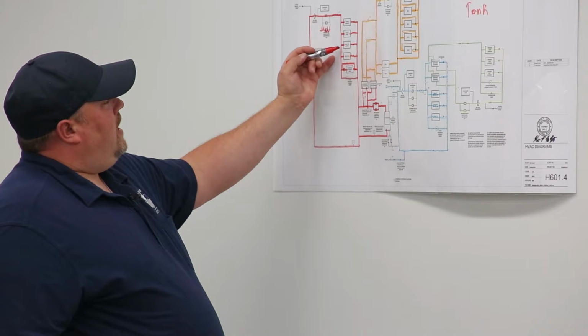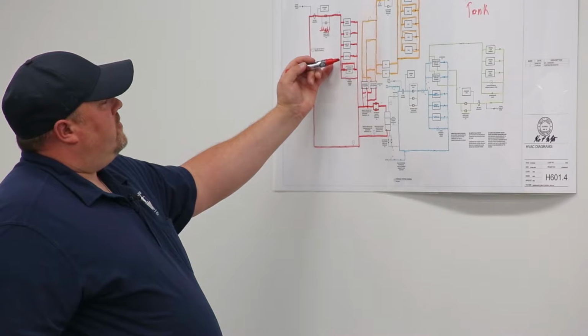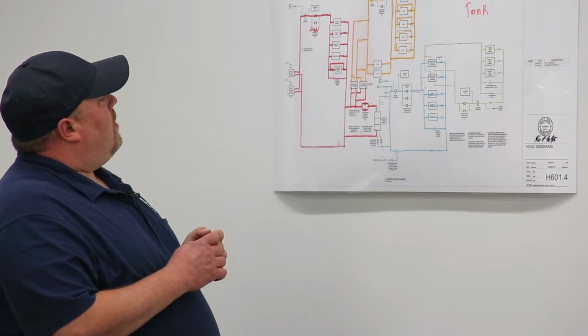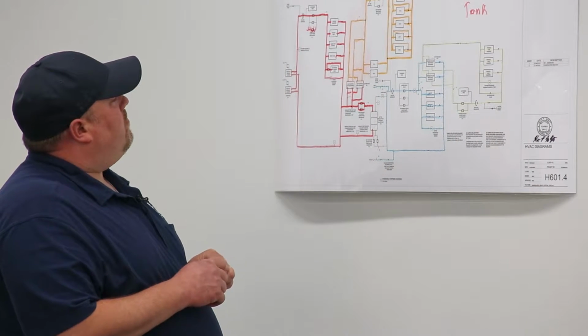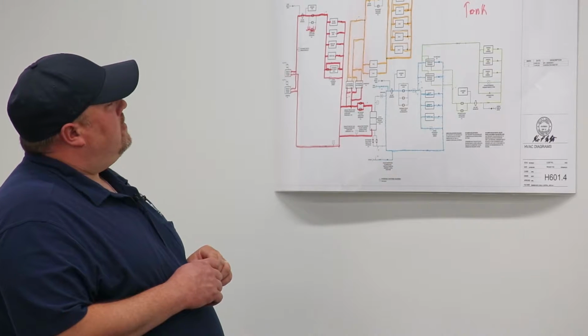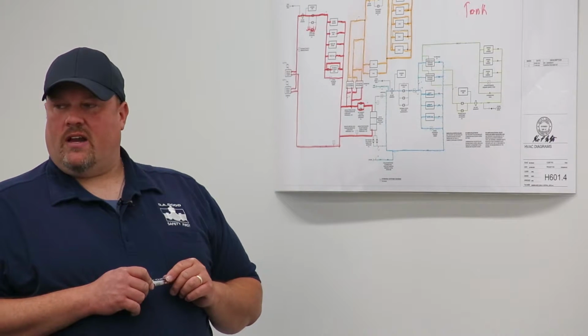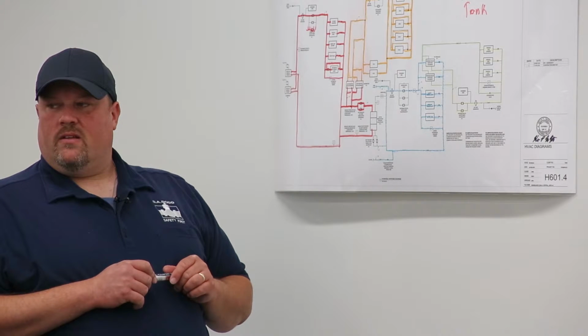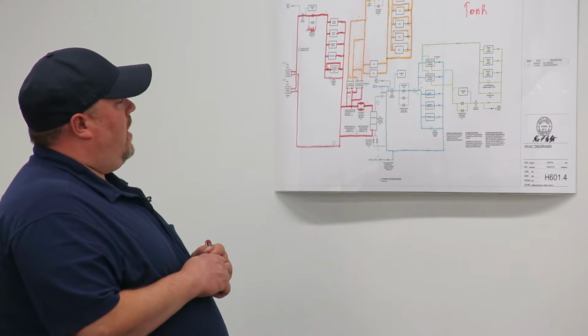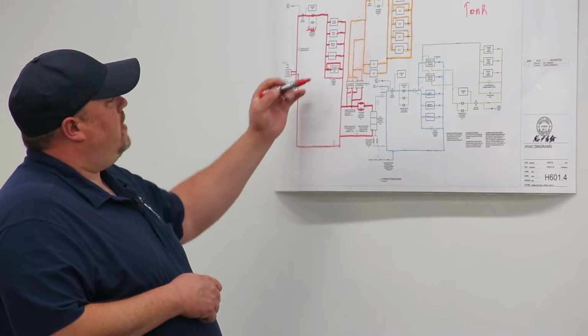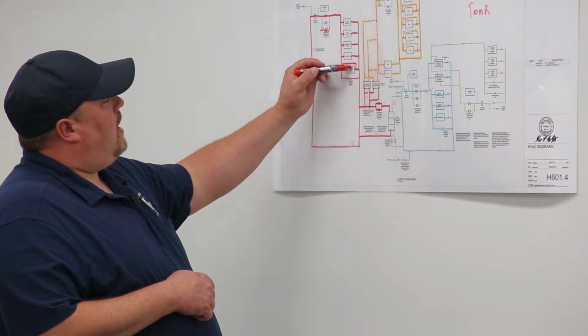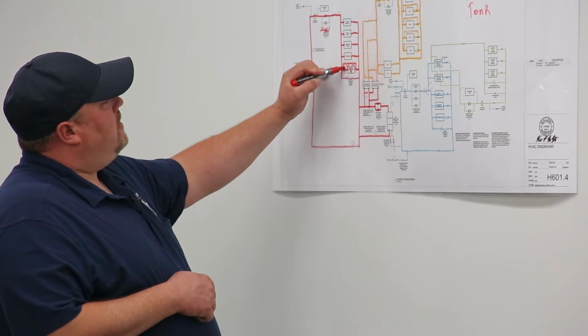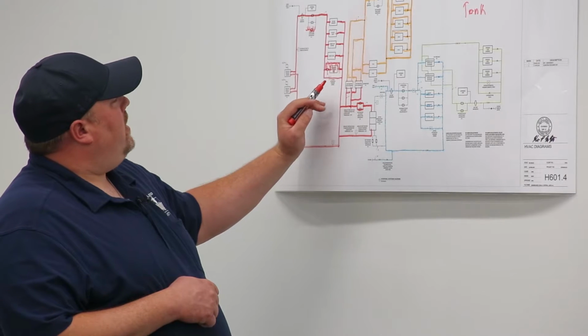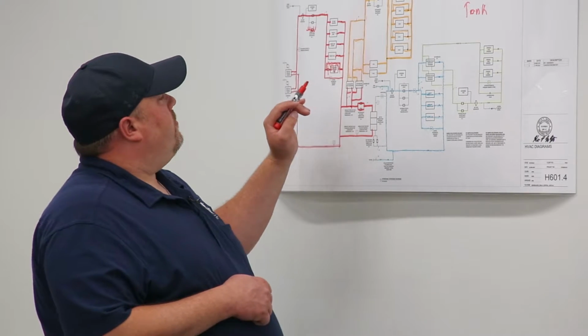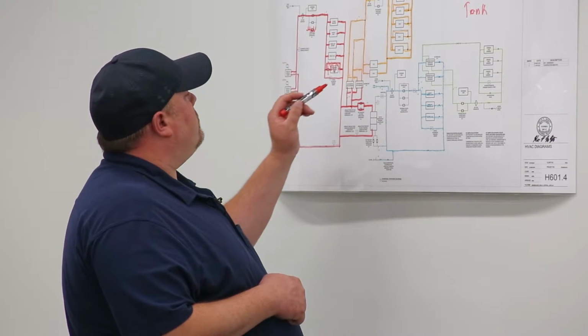This system here is no longer a set of pumps. This is a package, a skid pack, we call the Convecta package. This has a steam feed to it, which actually boosts the temperature of this loop to do the preheat on these air handler units. And this unit is circulated through here where we can actually pull heat from the exhaust fan coil units as it's exhausted from the building. It can recover as much heat as it can to also boost this loop to preheat these.